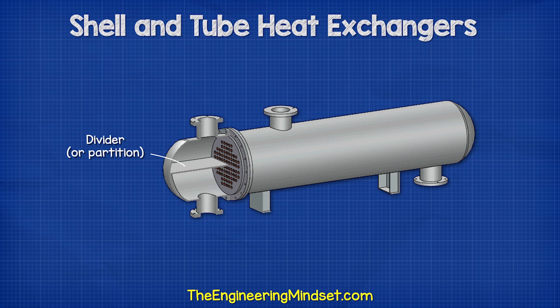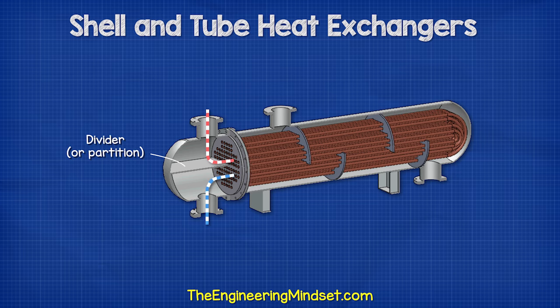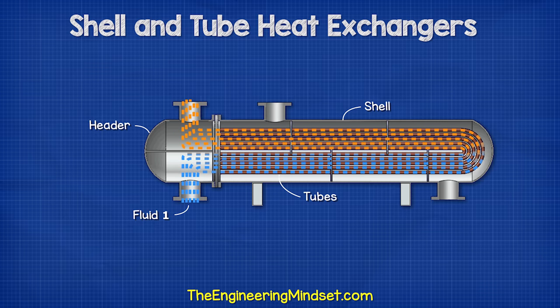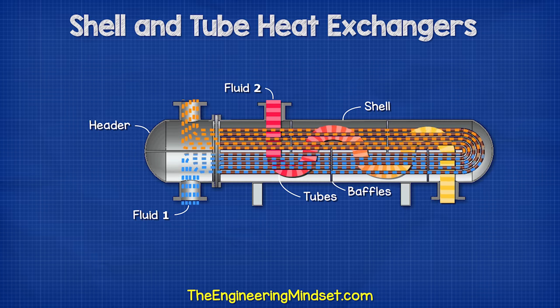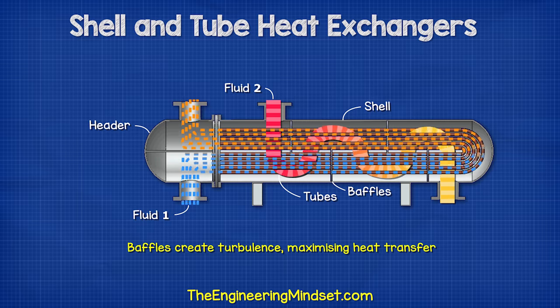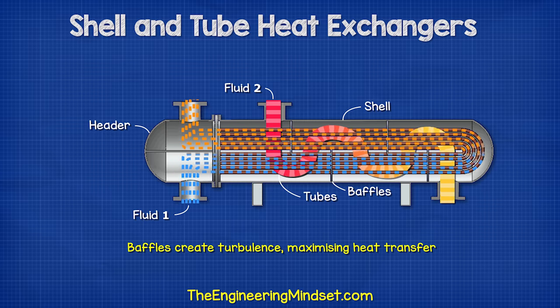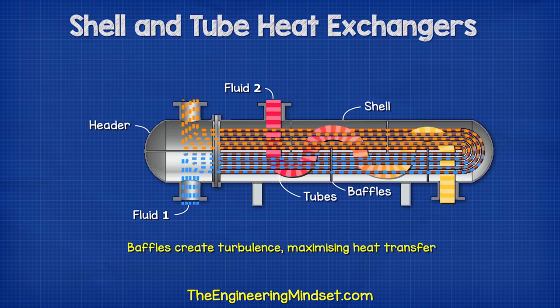Inside the header is a sheet of metal known as the divider or the partition. This separates the tube ends, enabling the fluid to flow into and then out of the heat exchanger tubes. Fluid 1 will flow through the header, into and around the tubes, then back to the header. Fluid 2 will enter the shell and surround the outside of the tubes. The baffles will partially block the flow, which will force the fluid to turn multiple times, creating a turbulent flow and ensuring that fluid 2 mixes with itself, which ensures maximum heat transfer.